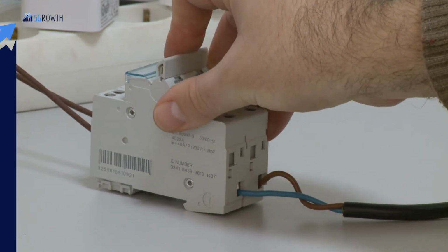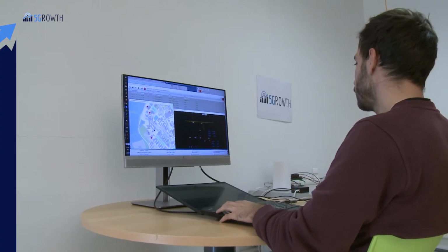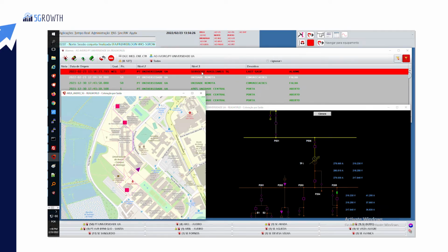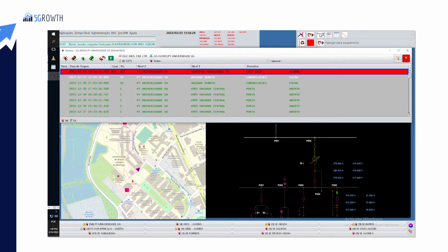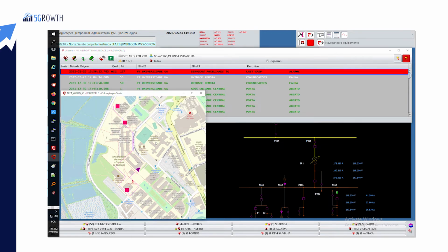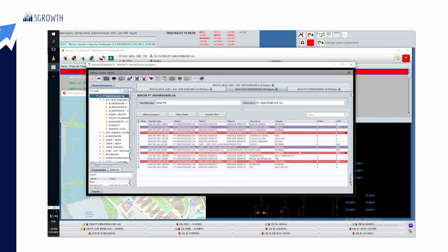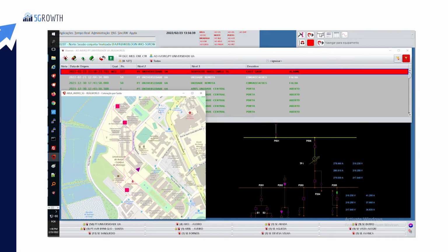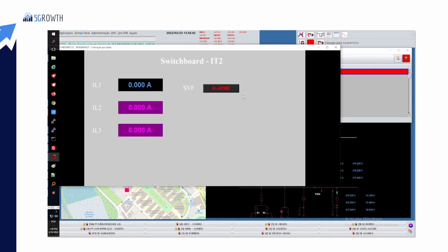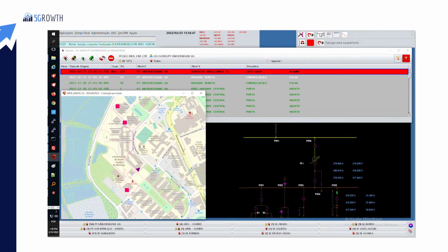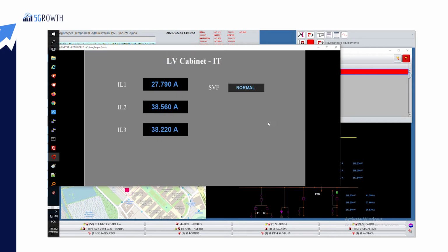We can see that as soon as the power supply is interrupted, a new alarm event shows up in the alarm list interface on the operator screen. Other user interfaces, like floating lists or diagrams, are also immediately updated with the new alarm status and the related telemetry measurements. The operator opens the diagram of the distribution cabinet close to the electrical switchboard and realizes that this one is still energized. The fault must be in the circuit between the distribution cabinet and the electrical board.